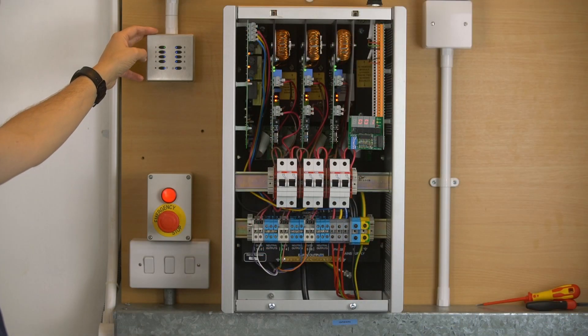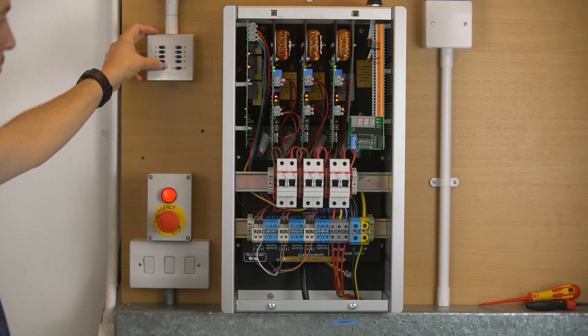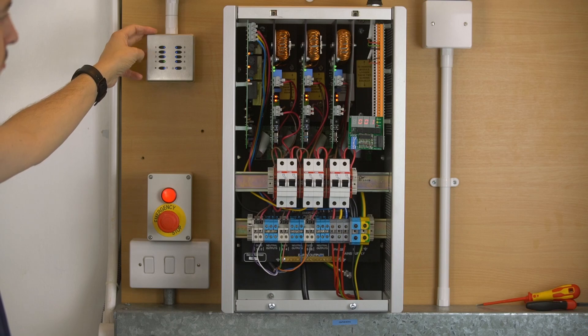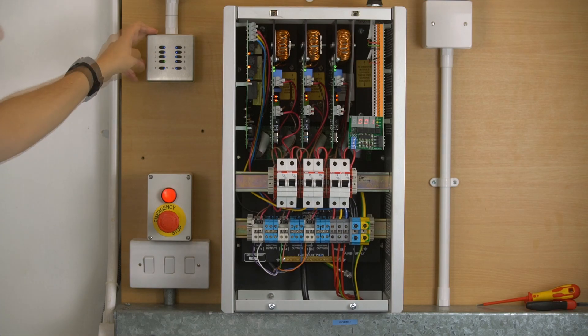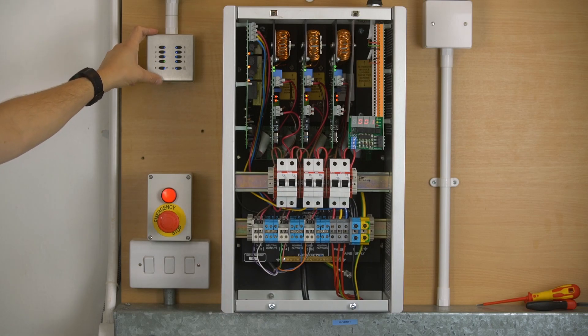We would then recommend pressing number four, which is 30% power output, and wandering around the site and seeing if all the lamps are dimmable as expected. If everything is going on and off, dimming down correctly from the keypad, you're ready for programming.